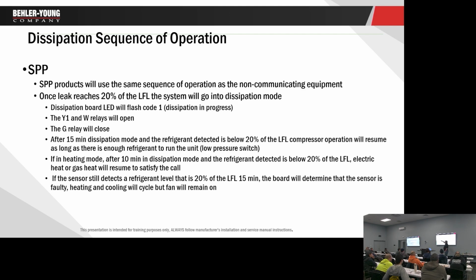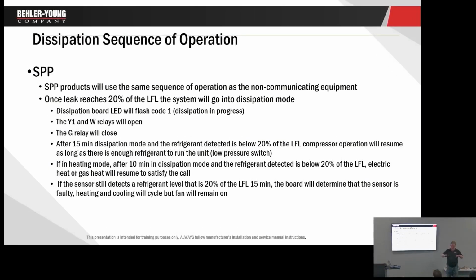So once we reach 20%, Y1 or W1 will open. Again, you do not have to wire this. This is all done internally. The blower will come on. The G relay will close. After 15 minutes of dissipation, if the level dropped below 20%, it will go back into normal operation. So the heat will come back on, the cooling will come back on. So if it dissipates within 15 minutes, it'll clear and go back to normal operation. In heating mode, after 10 minutes. So in heating, if it dissipates, it'll go back into operation after 10 minutes. Now, once that blower comes on, unless you got a gusher leak, it's going to clear it.